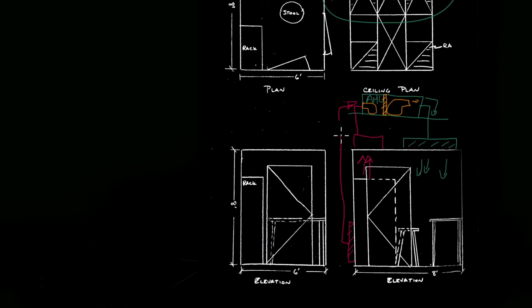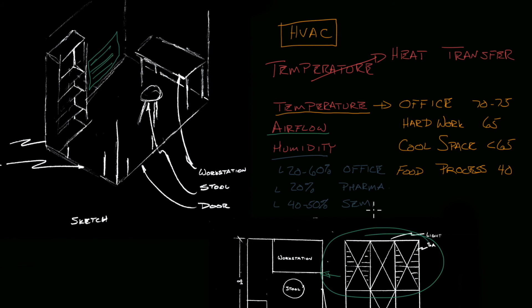Let's return to the top and talk briefly about humidity—the amount of moisture in the air. Generally in an office setting, we have a pretty broad latitude of 20 to 60%. However, in the pharmaceutical industry, we'll want lower humidity, say around 20%. This keeps water vapor out of the air, which can act as a host for bacteria. On the flip side, we might want to run 40 to 50% humidity in the semiconductor industry. Besides process demands, this also impacts static electric fields and keeps their impact minimal.